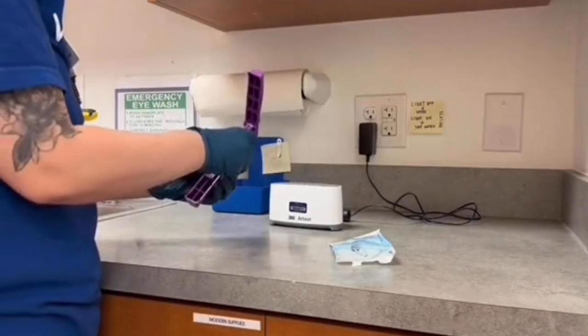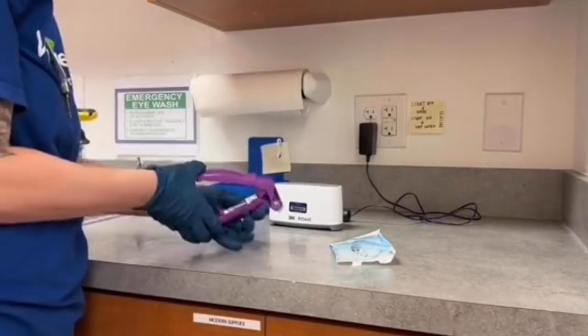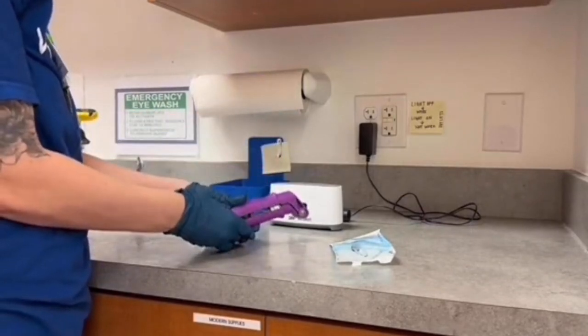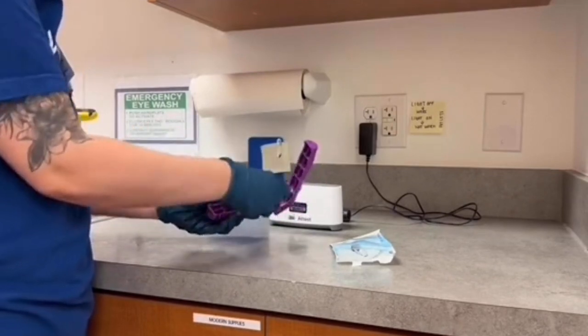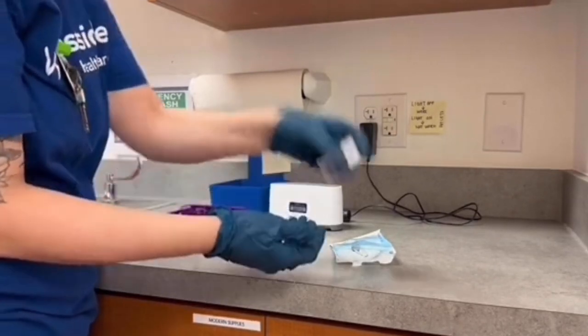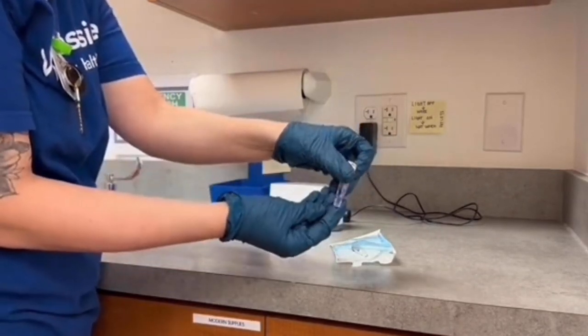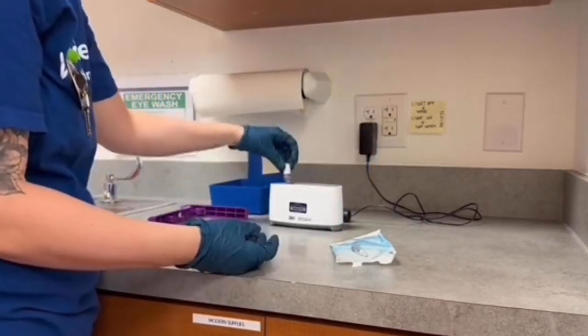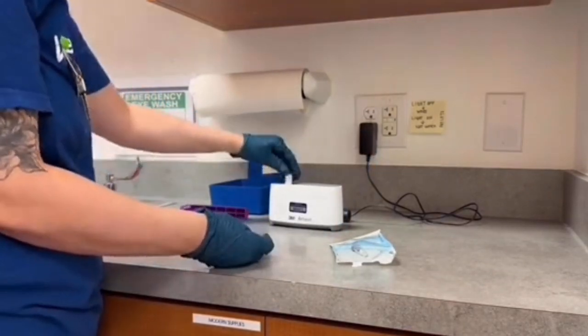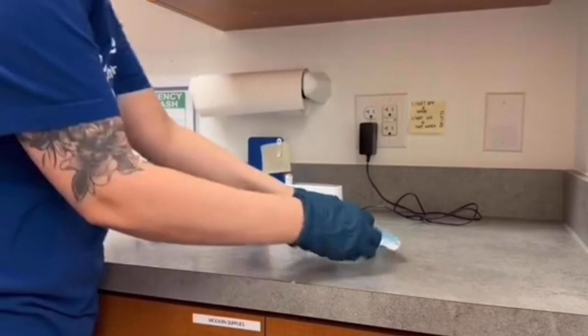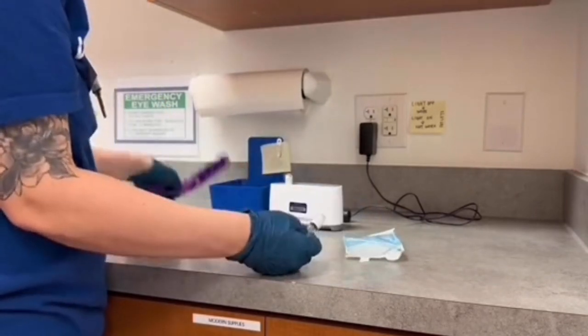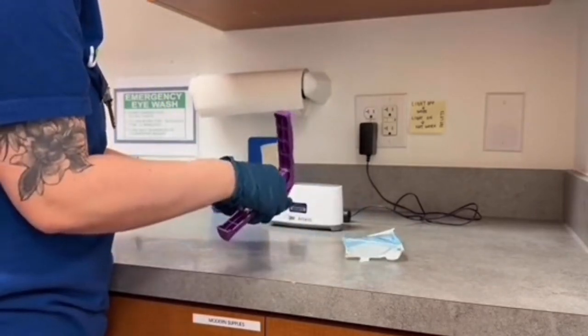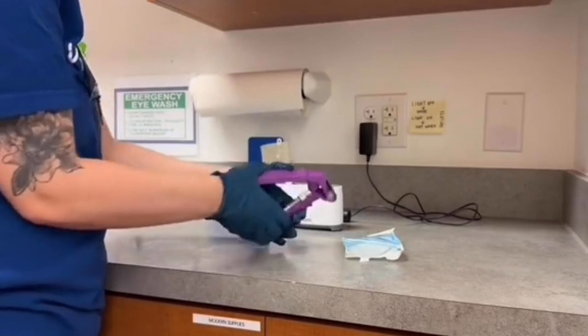The Attest Mini Auto Reader must heat up for at least 30 minutes before you use it. Start with a non-sterilized biological indicator called a BI. To activate it, place it in the activator and squeeze. Then place it into any of the chambers of the Attest machine with the color tab on the top. This is the control BI. Since this BI hasn't been sterilized, the result should be positive.